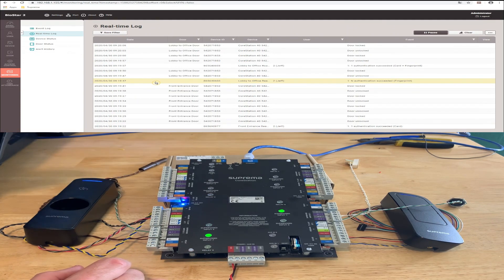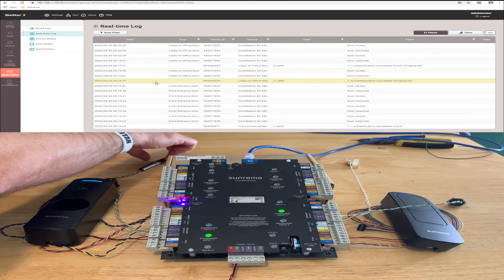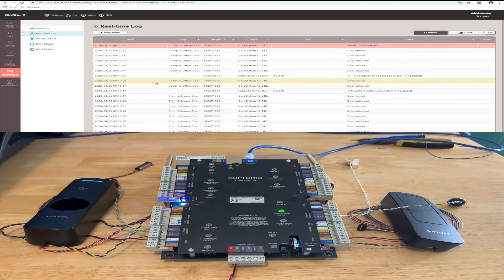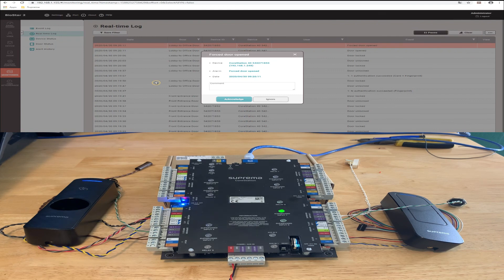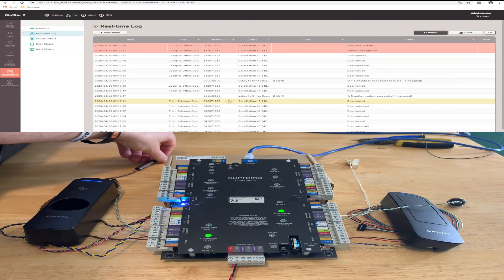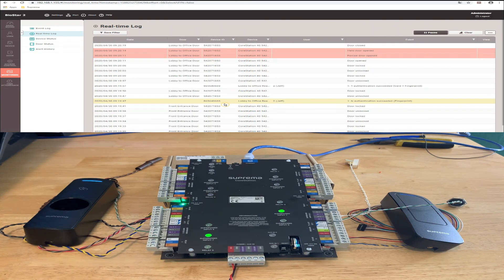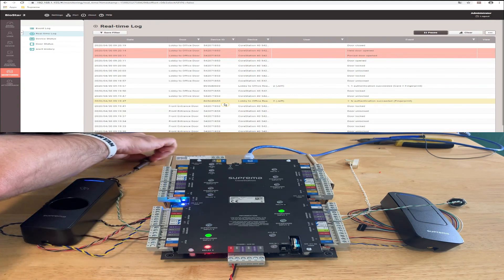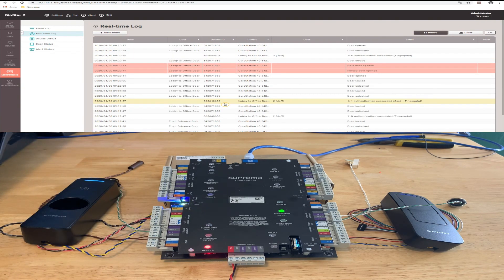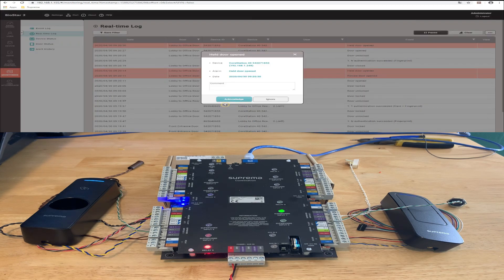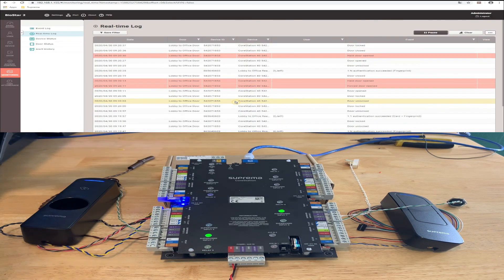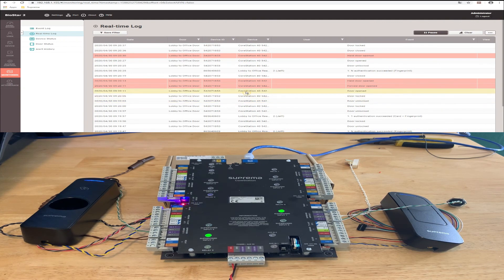And now you can see if I move the door contact magnet, I'll get a door forced. And I'll go ahead and acknowledge that. Return my magnet. And then I'll do a valid read. Remove the magnet and simulating a door held open. Now you get the door held open alarm. And that's it for configuring the core station with the X-Pass D2 and a BioEntry R2.